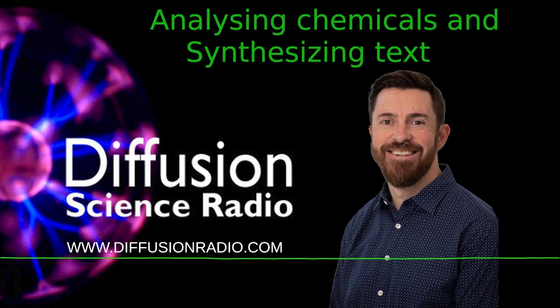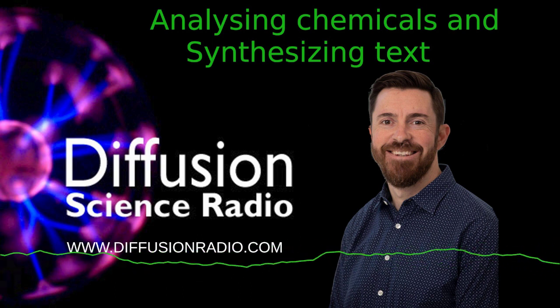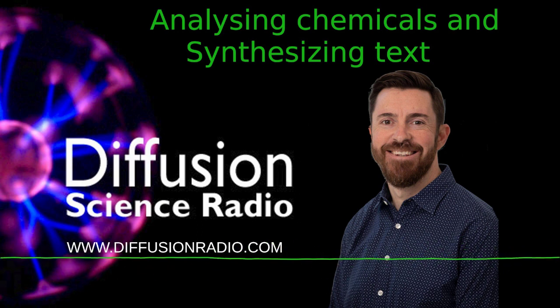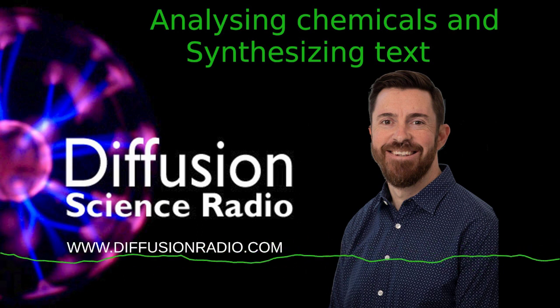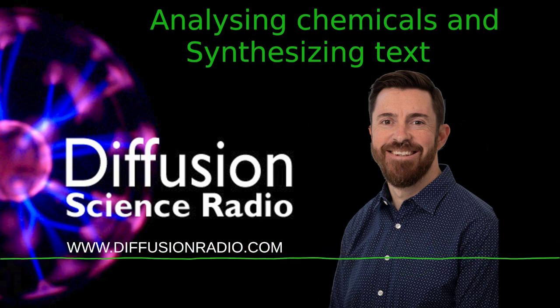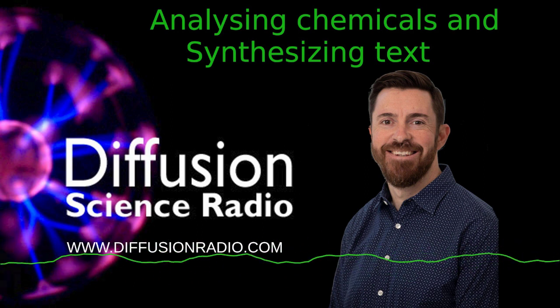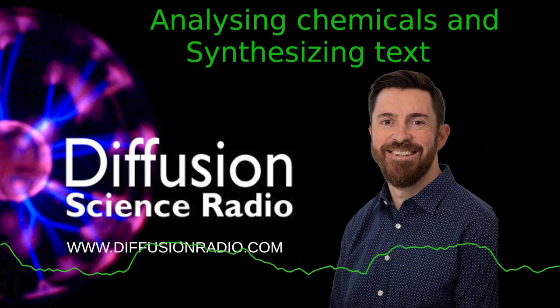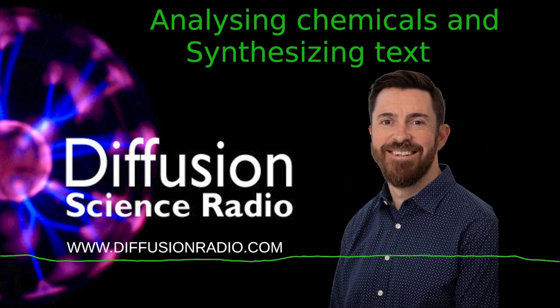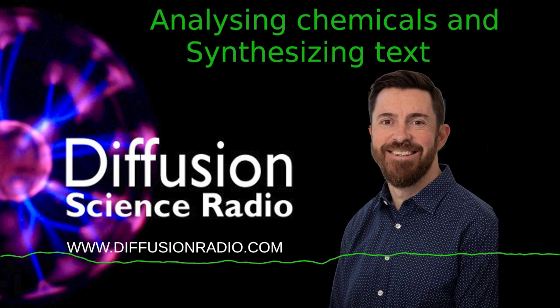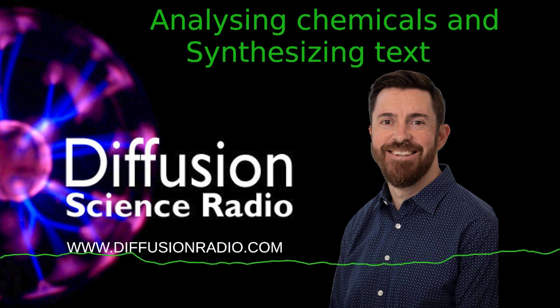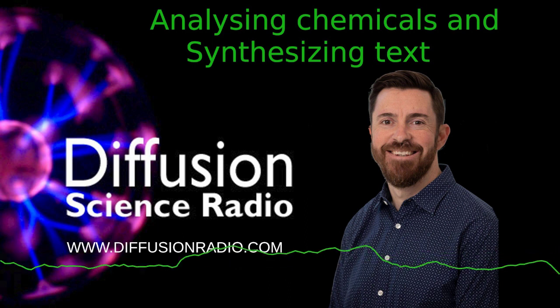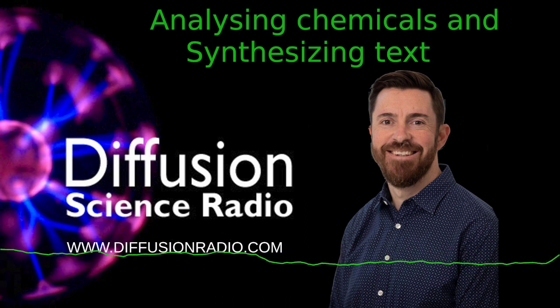And so how do these work? So there are a few main processes in ICP-MS. What we're trying to do is introduce an ion into the mass spectrometer. So ions are electrically charged molecules? Yes, correct. When we have a liquid sample, the first thing we need to do is form an aerosol. So it goes through a nebulizer to form aerosol, very fine droplets, and only droplets less than 10 micrometers will actually go through into the plasma.